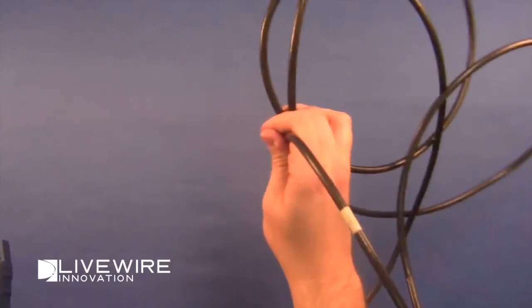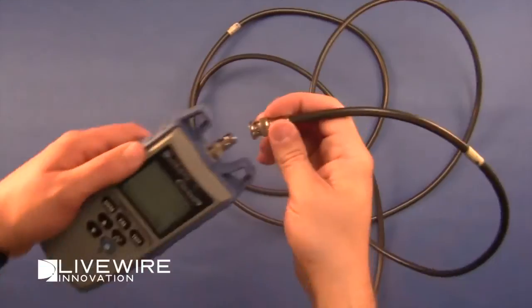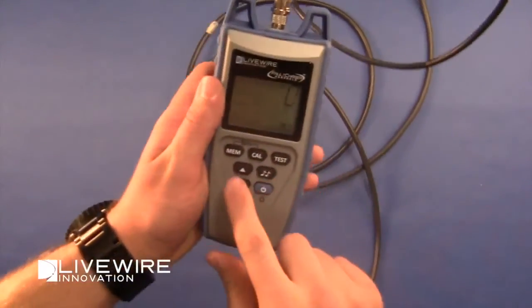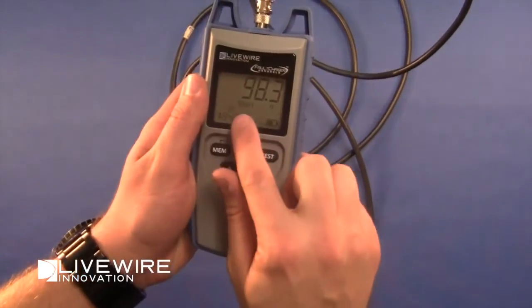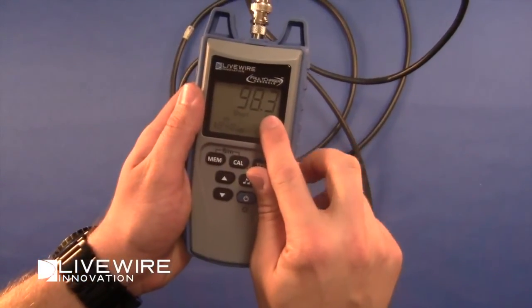Here's another example of detecting a short, this time using 900 feet of RG6 cable. The NVP value of this cable is 84.8. The Fault Chaser tells us that there's a short 98 feet away.